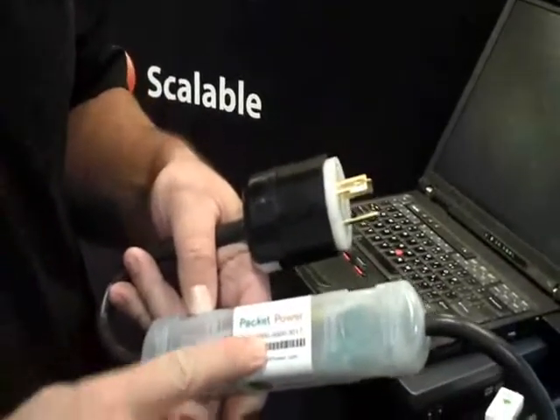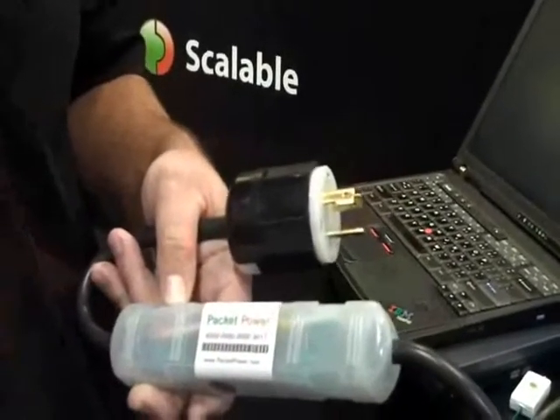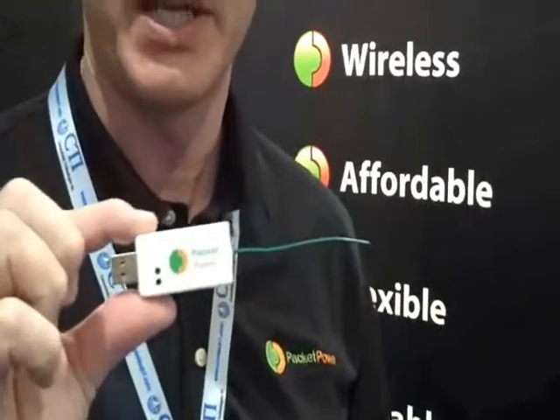The other thing that's in there is a radio. So all of our cables can talk to each other. They form a self-configuring wireless mesh network. And within range, that mesh needs to be one of these — this is our USB gateway. It plugs into the USB port on a Windows PC. It gathers up information from thousands of the cables. As long as it can talk to one cable, it needs to be within a couple hundred feet of it. It can get information from all of the cables in the mesh.